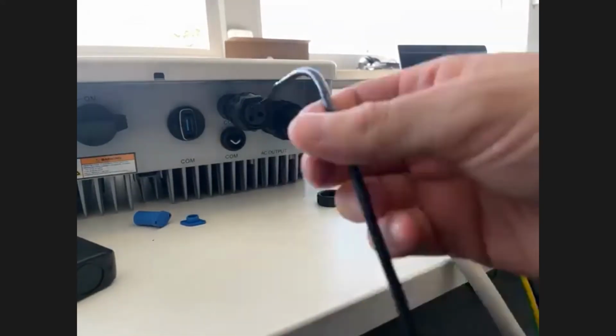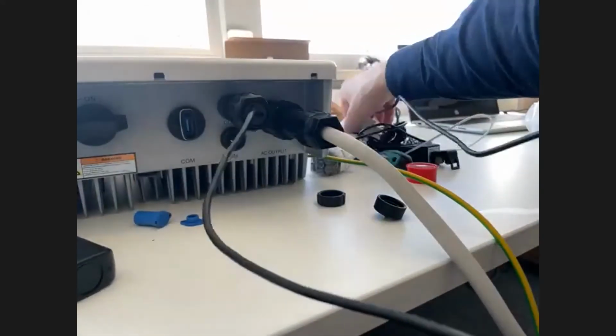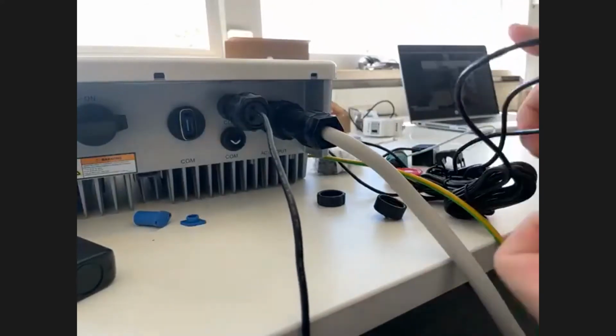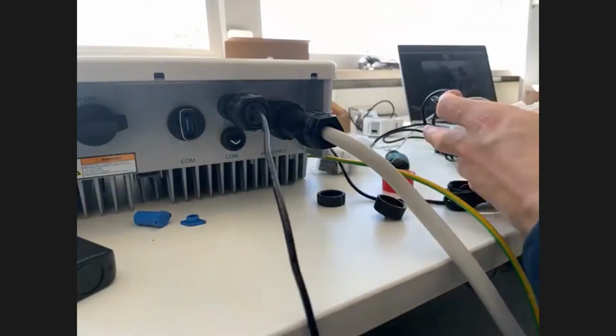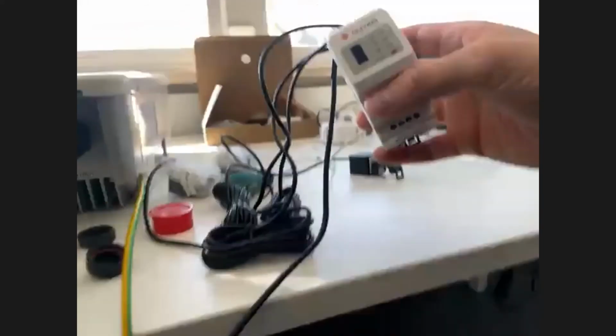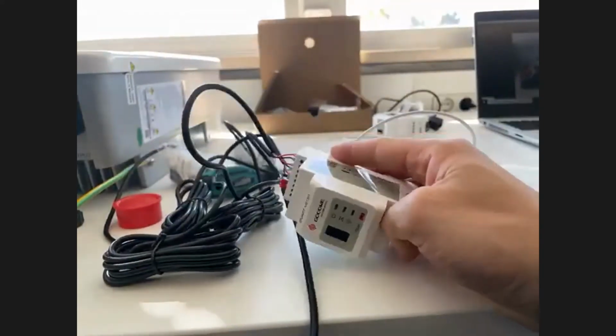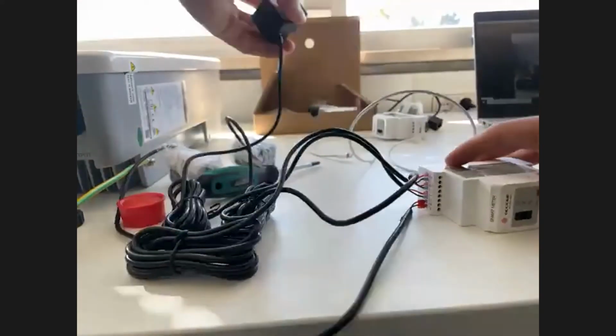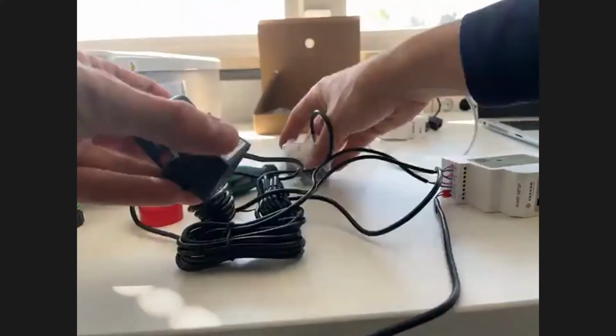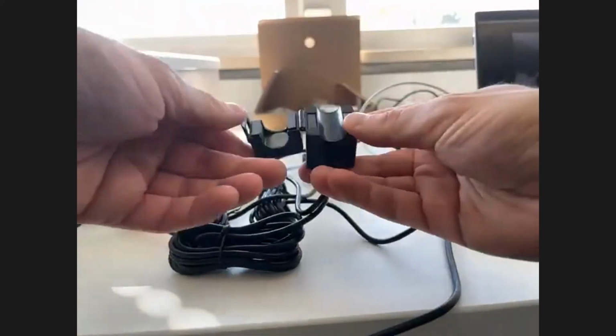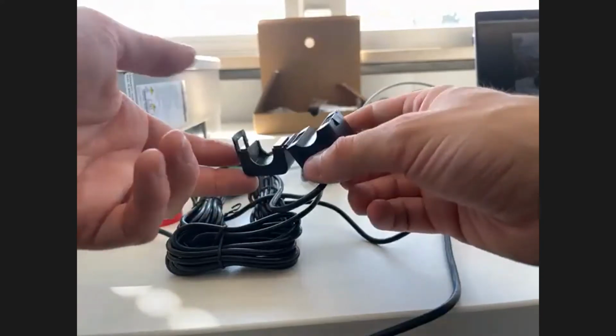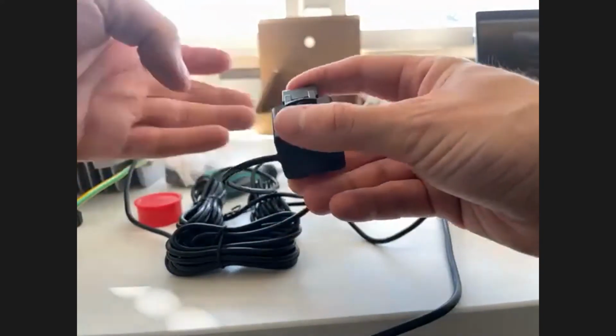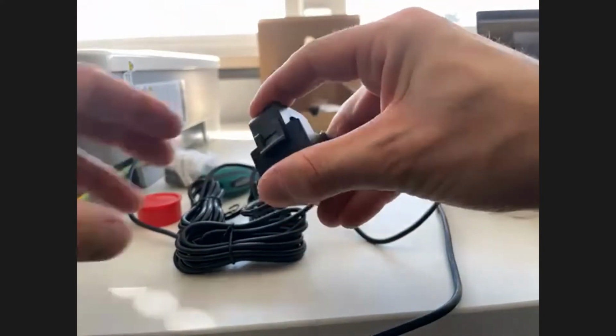Yes, and the other cable here, the RJ45, that goes to the smart meter here. And then, just to make sure that you see everything, connected on top here, you have the CTs. And the CTs are quite straightforward. They're just CT clamps. So you just put the cable in here and then close it like this. There's a small click.